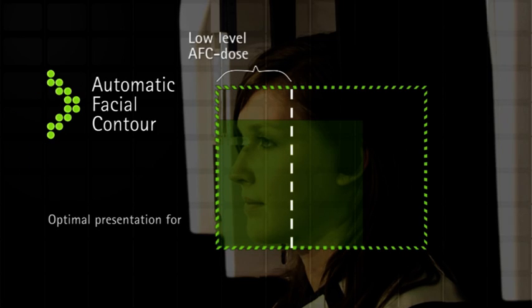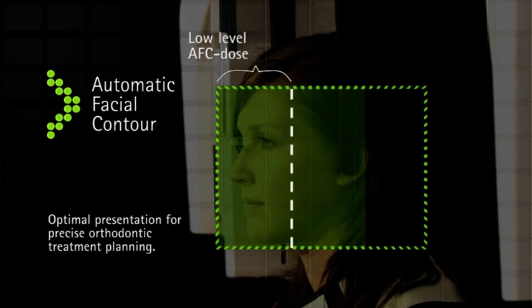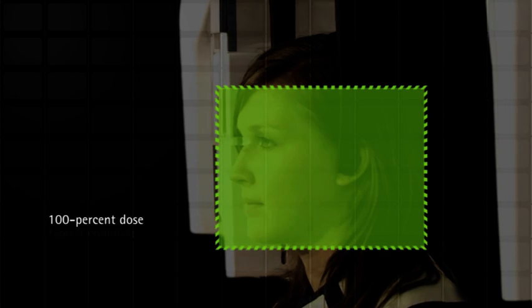The soft tissue structure is shown extremely well with the automatic facial contour in the remote x-ray function. The imaging area can be collimated and allows adapted projections with a considerably reduced patient dosage.